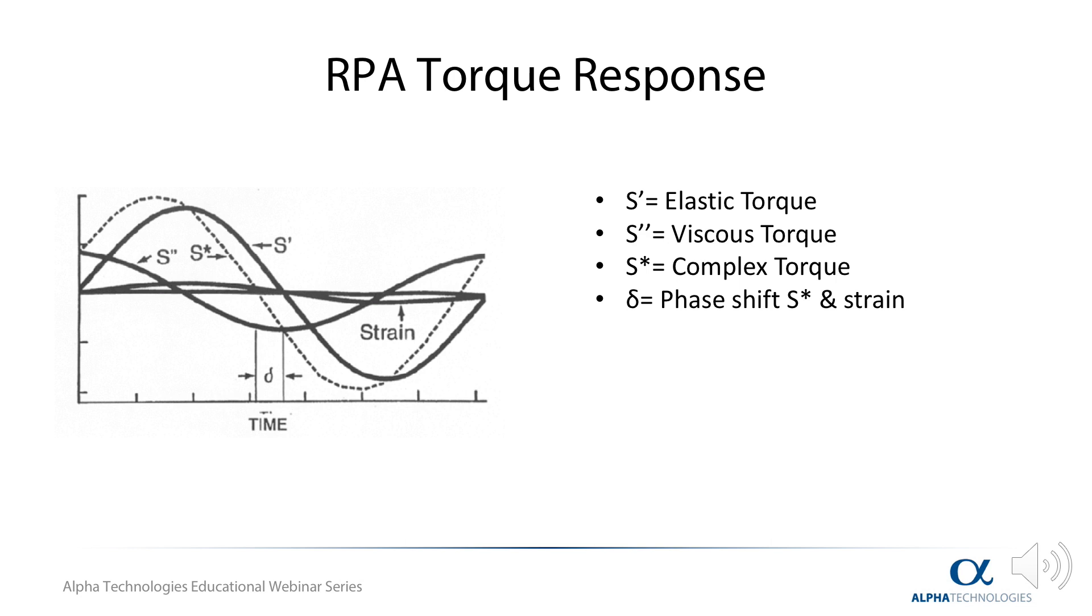As shown, this complex torque is out of phase with the applied strain. A Fourier transform is applied to the complex torque curve and used to separate the complex torque, otherwise referred to as S star, into two additional curves. The first is an in-phase torque signal, S prime. The second, a 90-degree out-of-phase signal, S double prime.